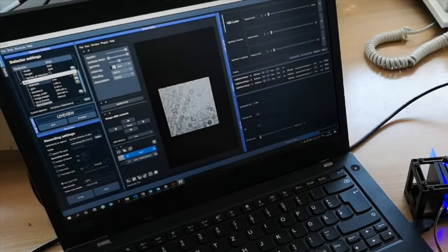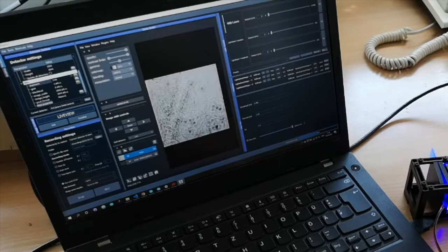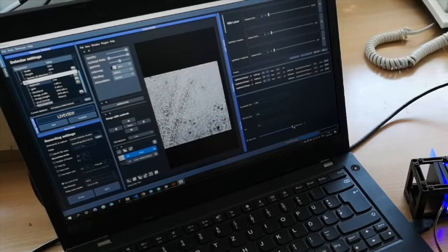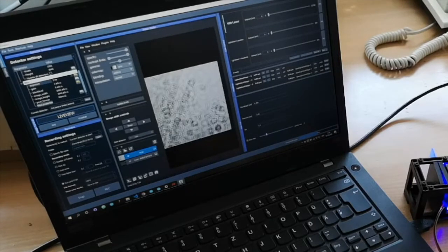When we tune the focus, you already see that you can numerically refocus the dust that's sitting on the cover slip. At one point the spots here become very small, and that means you are in focus with respect to the dust. You can refocus, and then they go away again. And the rings are an artifact from the inline holographic setup. This is just due to the method itself.